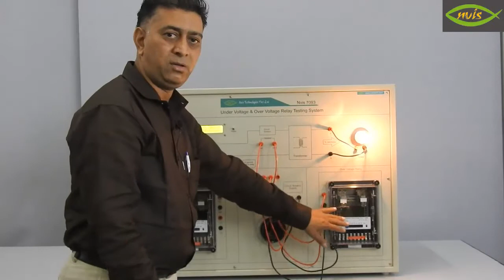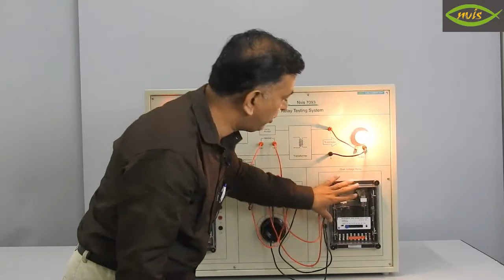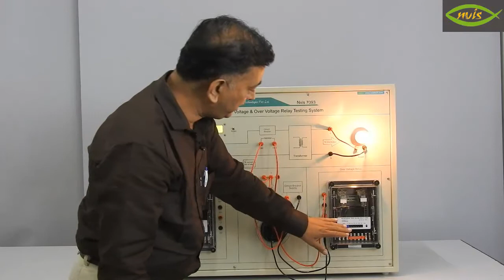Similar to the under voltage relay, the over voltage relay also has plug settings. Various plug settings are given: 121 volt, 126 volt, 132, 137 and so on up to 154 volt. Any one plug setting we can choose, and here also 4 screws are given with which you can take out the transparent cover and change these plug settings. The desired plug setting can be set; that totally depends on your circuitry and your load. After setting the plug, you can see and note this. Right now we set it for 121 volt. So this system should be tripped at 121 volt. We can increase the voltage up to 121 volt, and after 121 volt my transmission line should be disconnected and my load should be protected.